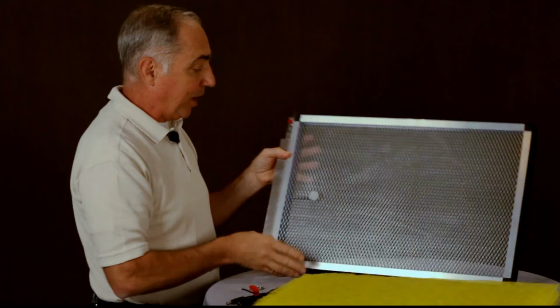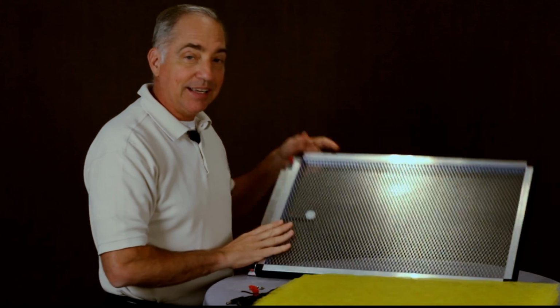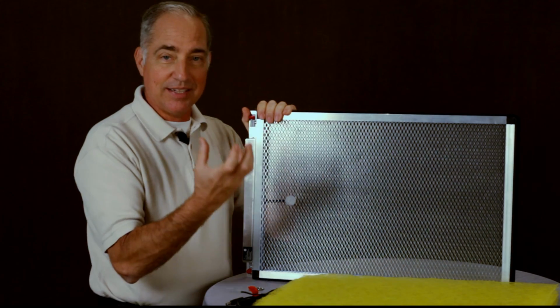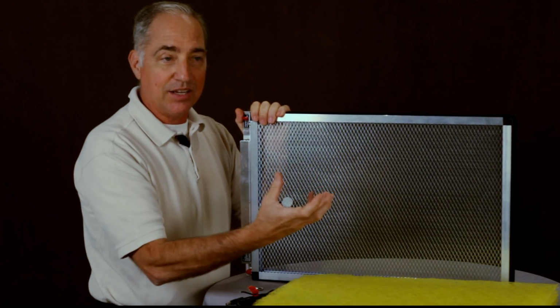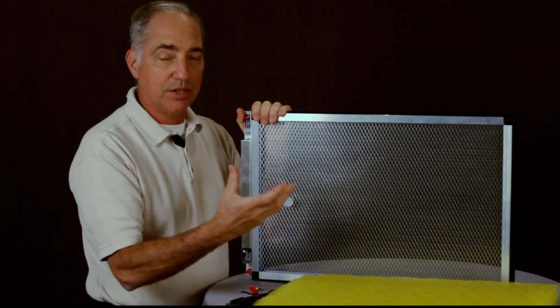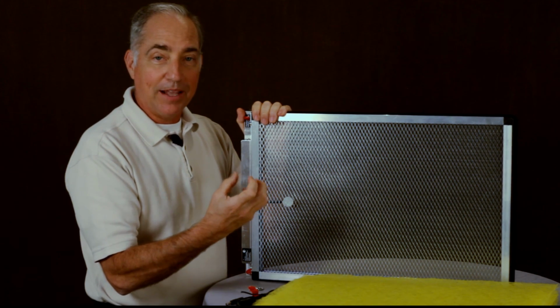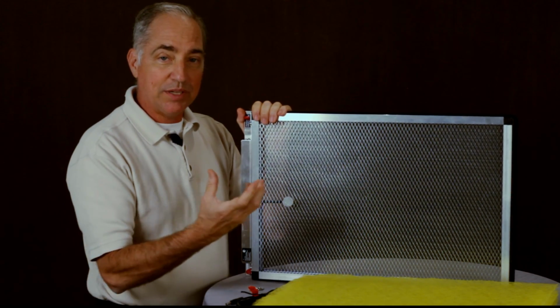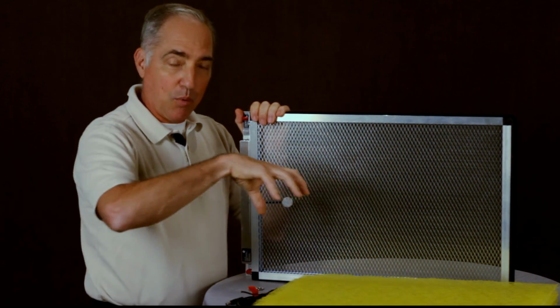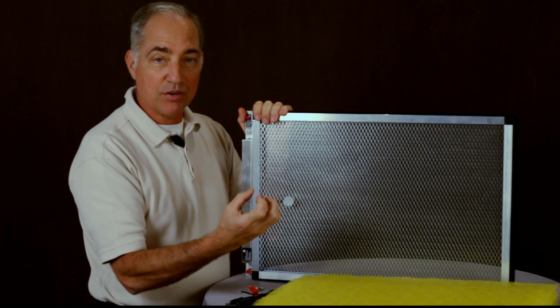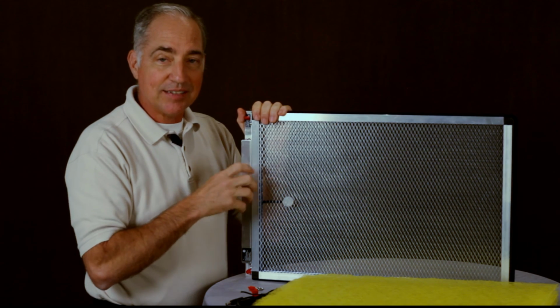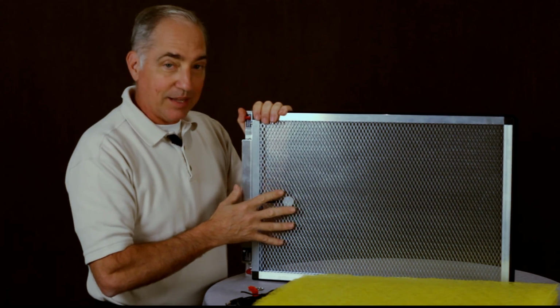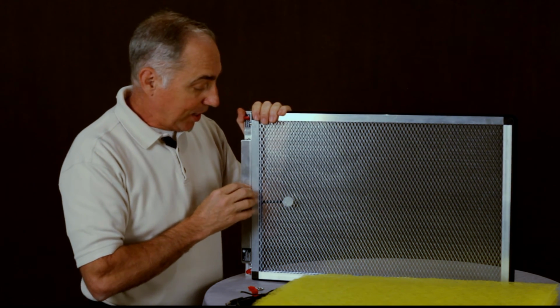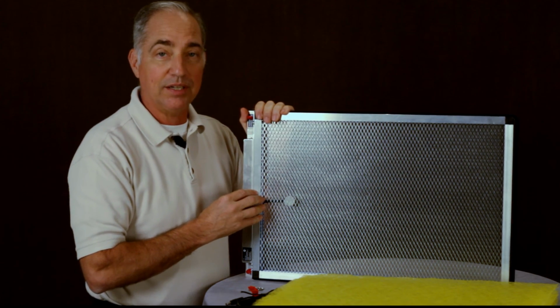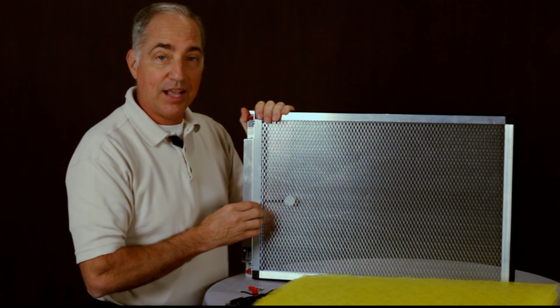So we've got the power head that induces 7,000 volts of DC energy onto the pad. And it's a potted electronic board. And what that means is, if you have an open electronic board inside ductwork, you're going to get moisture, mold, dirt, dust, and debris build up on it, and it'll heat it up, and then they burn out very quickly. So with a potted electronic board, we take the same electronics and we put it in a mold, and they pour liquid plastic over it, and it hardens. Now it's encased in plastic. And we put heat sinks in there to dissipate the heat. So we're going to get basically a bulletproof power head. You've got a power head in here that's going to last a lifetime. That's how we get a lifetime warranty. Our failure rate on these power heads is less than 1/10 of 1%.